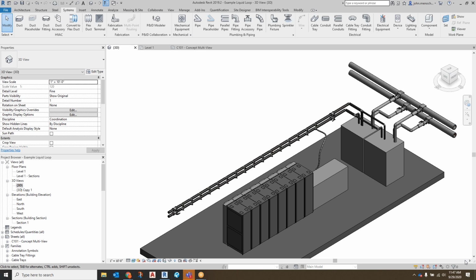As far as the pipe velocity piece goes, I know standard is a bad word in the data center industry, but 90.1 actually has guidelines for pipe velocities, and it's all energy driven. When you compare those pipe velocities to what is typical best practice for hydronic system design, it pretty well aligns. So if we want to reference a standard, I think that would be a good one, especially given that there's usually very tight alignment between 90.1 and the IECC.